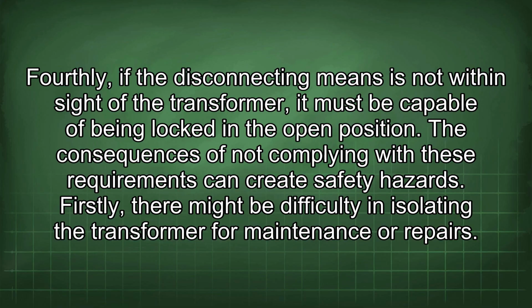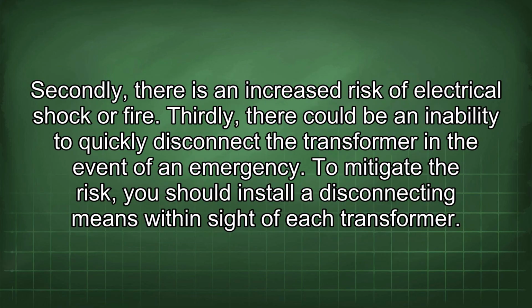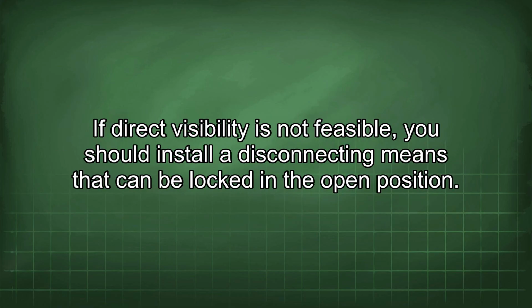the open position. The consequences of not complying with these requirements can create safety hazards. Firstly, there might be difficulty in isolating the transformer for maintenance or repairs. Secondly, there is an increased risk of electrical shock or fire. Thirdly, there could be an inability to quickly disconnect the transformer in the event of an emergency. To mitigate the risk, you should install a disconnecting means within sight of each transformer. If direct visibility is not feasible, you should install a disconnecting means that can be locked in the open position.